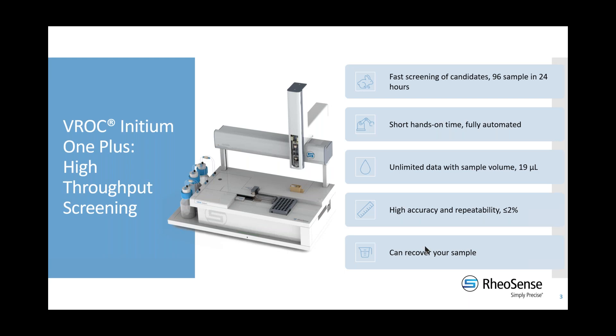You also have the option to recover your sample so you don't need to use more of your precious sample for further testing. This allows you to test large libraries of biological molecules, reducing the time needed to find your leads and exclude other candidates. I'm going to show how to obtain viscosity results with this high throughput screening mode, with volumes as low as 19 microliters, through slides as well as a webcam demo.